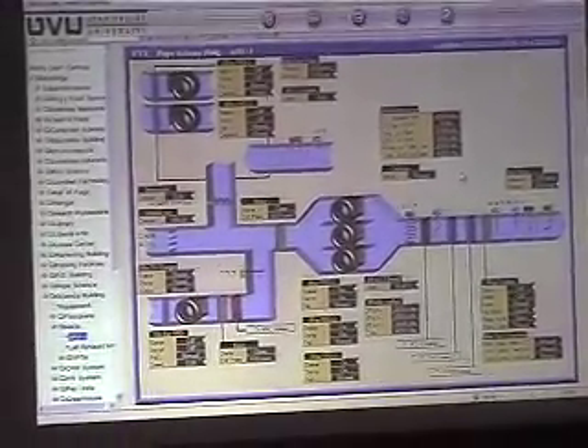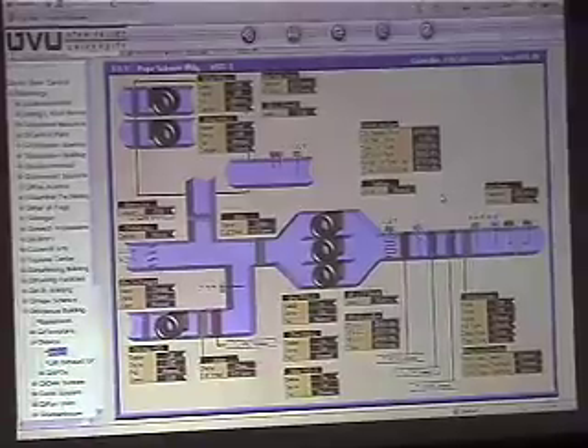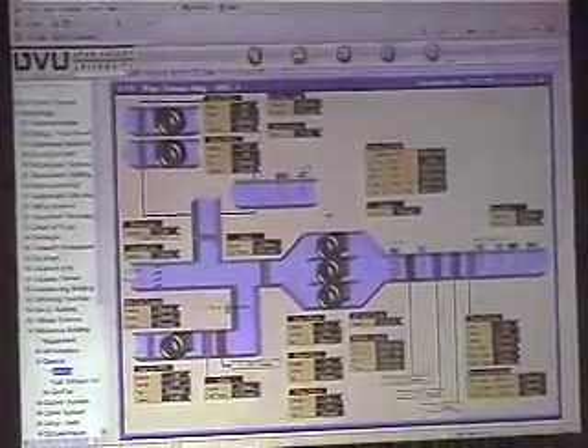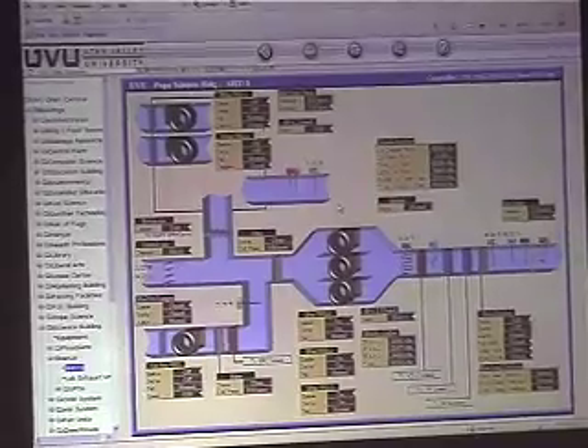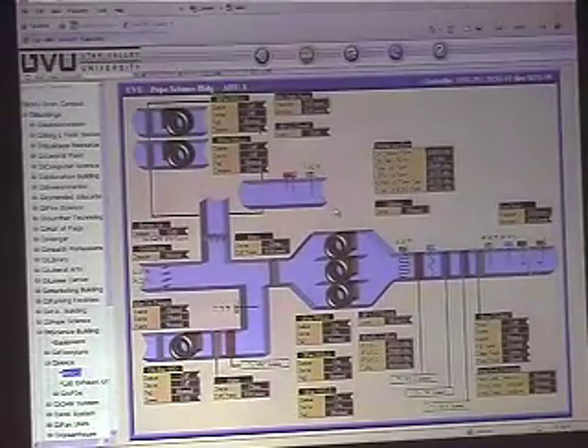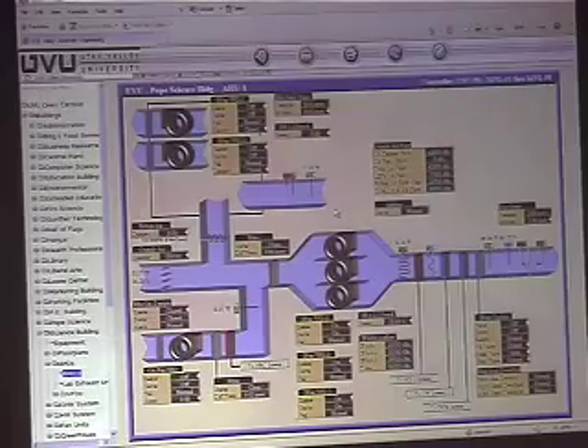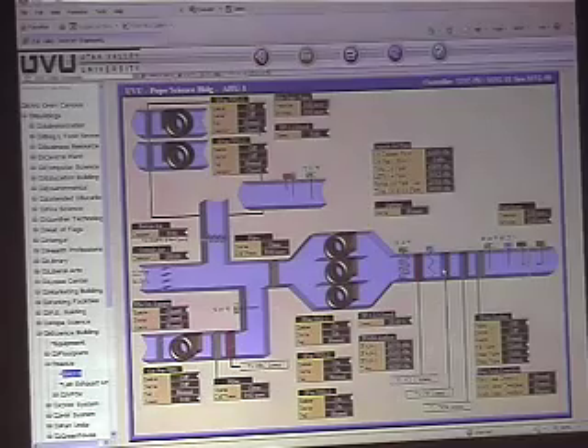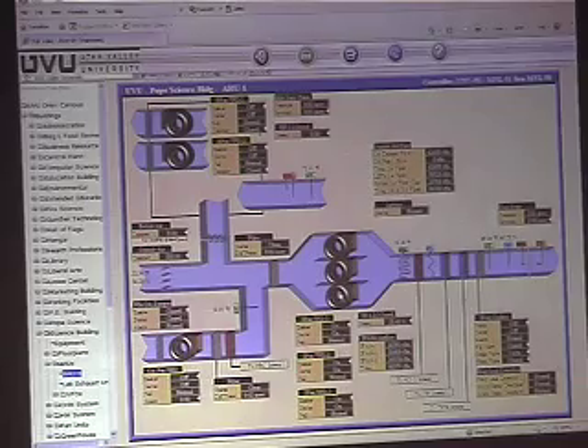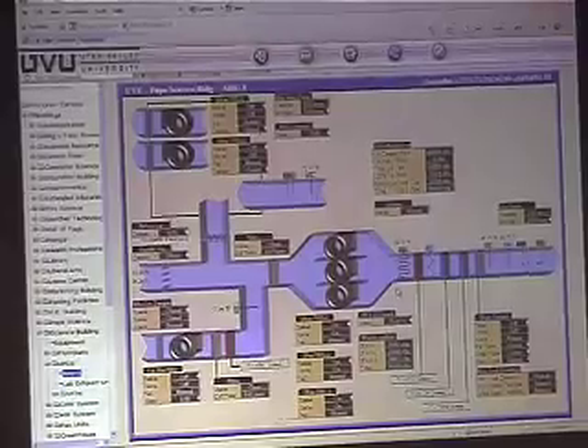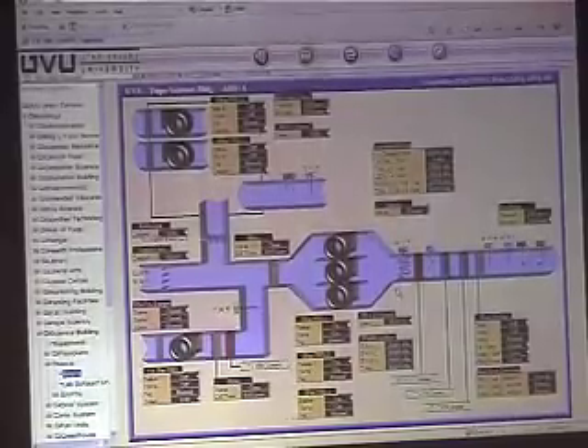So with the air handler here, it's pretty much the same setup you're familiar with on the rest of your buildings as far as the graphics go. You've got your supply fans here, your coil representations here. This air handler has 3 supply fans in it, each one controlled off of a VFD. One speed signal controls all 3 fans, so they operate simultaneously. They're meant to all operate together.